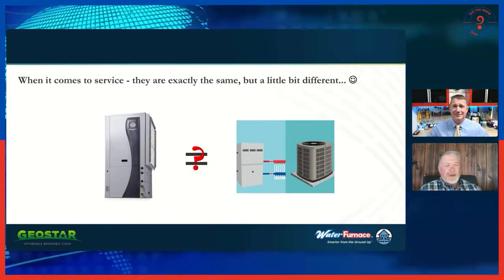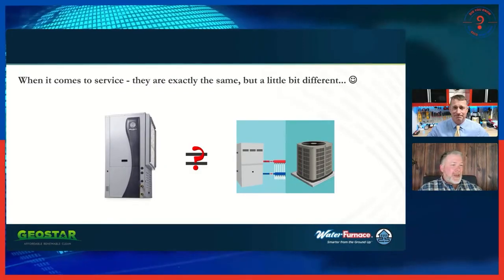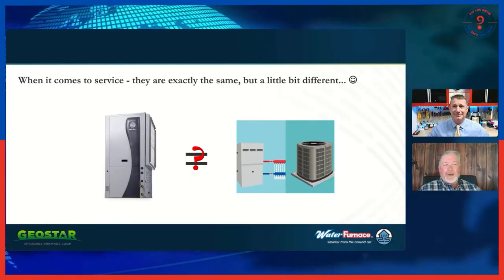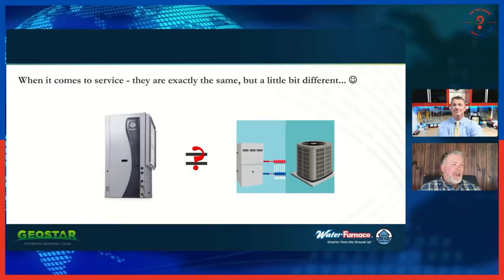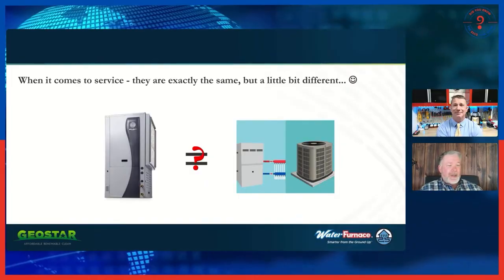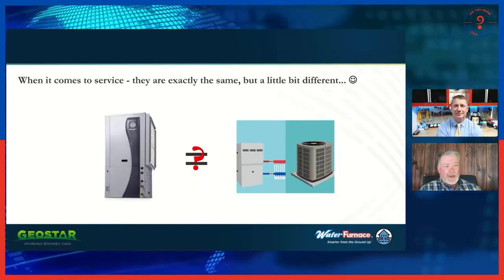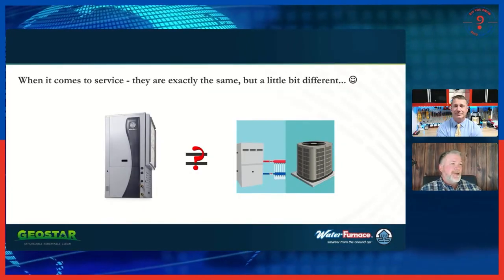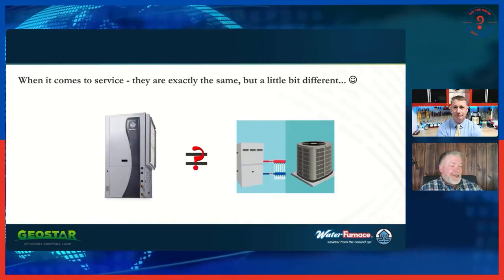So really, in general, what causes high pressure is lack of flow across the condenser. That's it. In our case, if I'm running air conditioning with my geothermal heat pump, my condenser is my coax heat exchanger. That's where the condensing is happening.